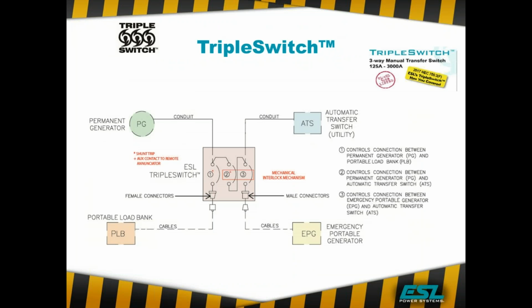So here is how the triple switch is set up. You can see how all of the connections come together. You can see here that the load bank has a shunt trip on it. This is your load bank connection. Then you have your ATS to permanent generator connection and your portable generator to ATS connection. Those two are mechanically interlocked, so only one of them can be on at a time. And then you have an aux contact on this middle breaker, because when that is shut off or opened, that means the permanent generator cannot provide power to the ATS. So that's where we signal that the permanent generator is now offline.